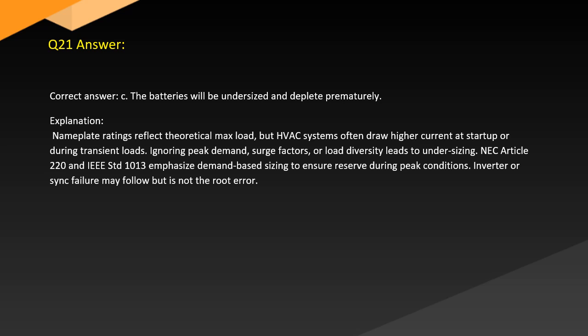Answer. Correct answer: C. The batteries will be undersized and deplete prematurely. Explanation. Nameplate ratings reflect theoretical max load, but HVAC systems often draw higher current at startup or during transient loads. Ignoring peak demand, surge factors, or load diversity leads to undersizing. NEC Article 220 and IEEE Std 1013 emphasize demand-based sizing to ensure reserve during peak conditions. Inverter failure may follow, but is not the root error.